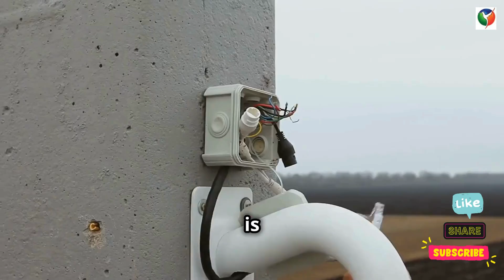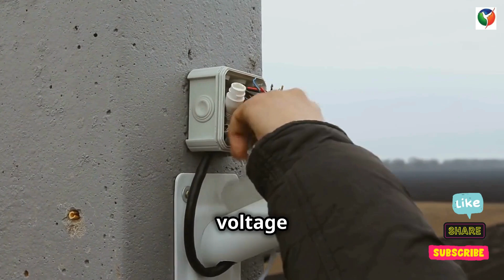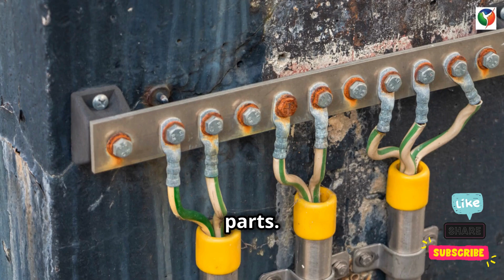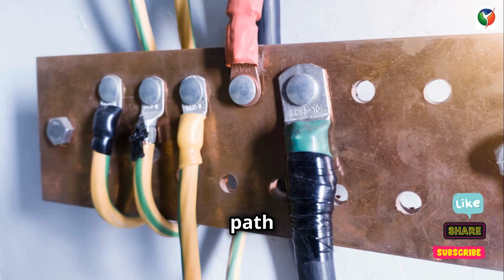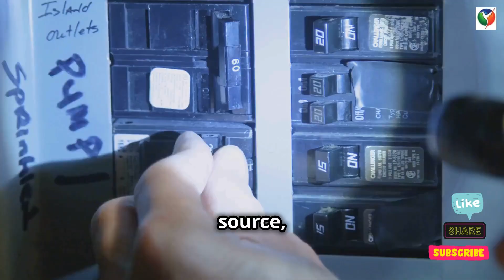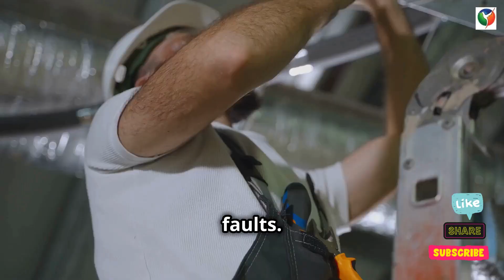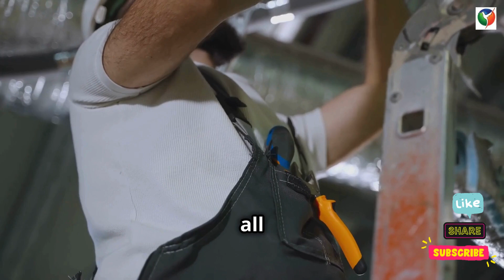The purpose of bonding is to prevent dangerous voltage differentials that could cause shock hazards between metallic parts. It provides a continuous low resistance path for fault current to return to the source, ensuring the protective devices, like circuit breakers, trip properly during faults. Ultimately, bonding ensures safety by keeping all exposed metal parts at the same voltage, typically ground voltage.